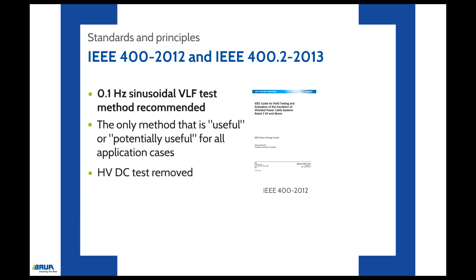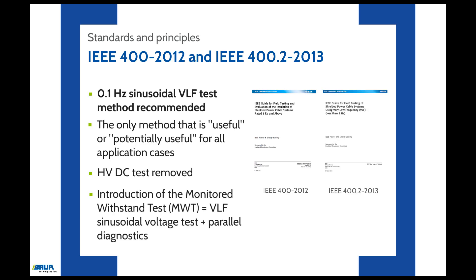Moreover, the HVDC testing of XLPE cables is no longer recommended due to bad experiences. Following the introduction of IEEE 400.2, 2013, the TAN-delta monitored withstand test was introduced onto the market. This means the performance of the VLF sinusoidal voltage test with simultaneous diagnostic measurement.